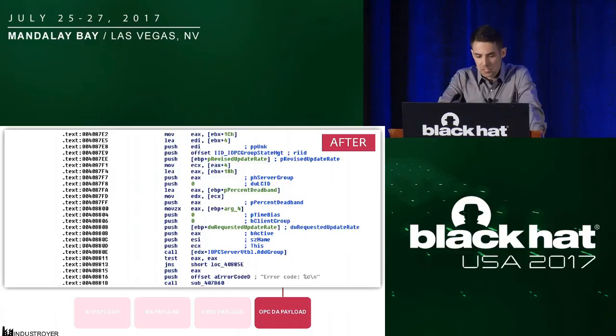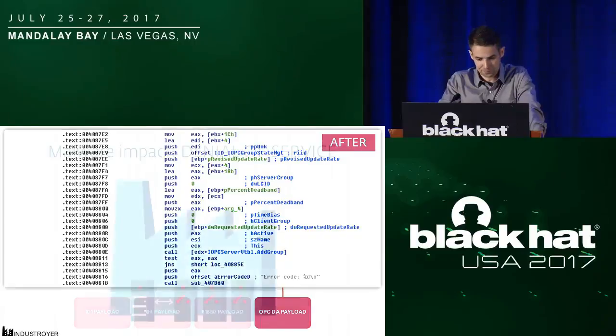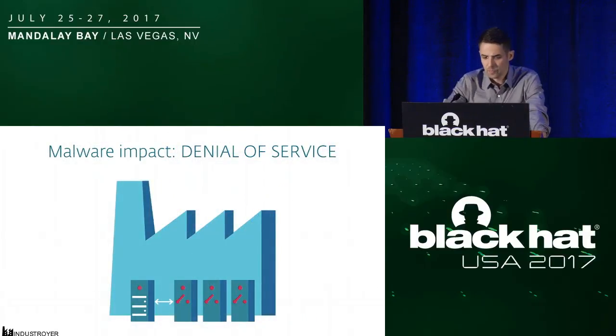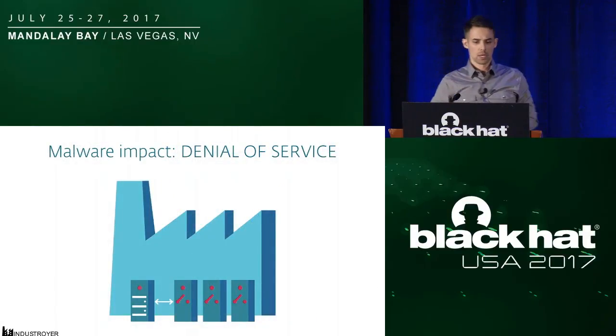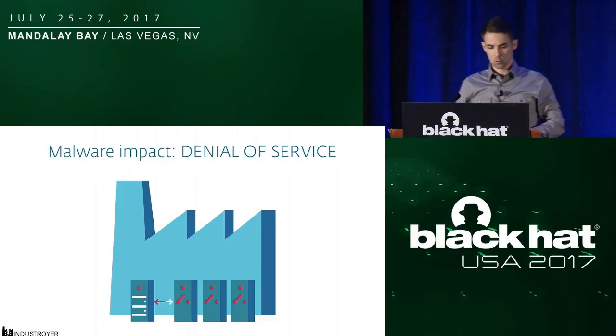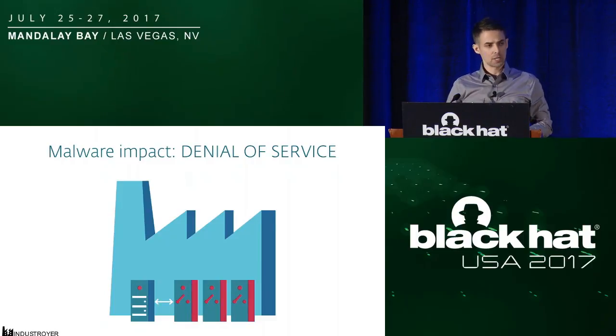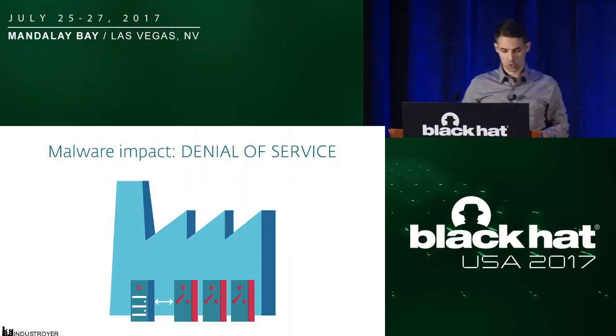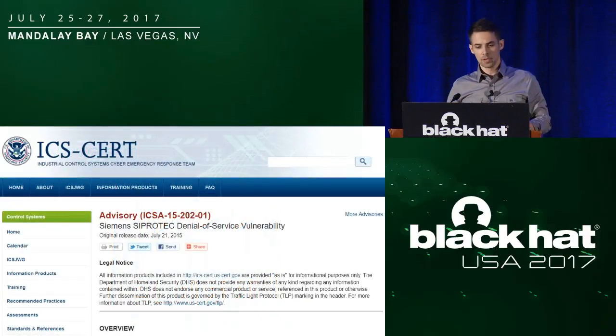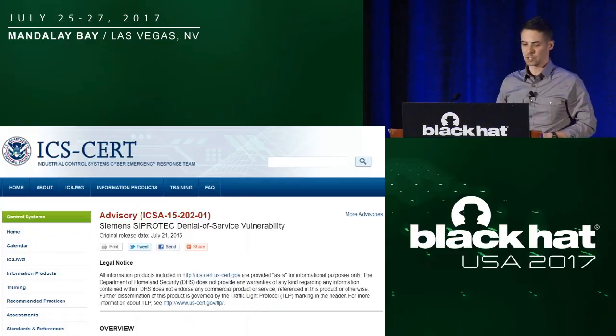De-energizing a substation is the most obvious impact scenario, and Dragos will go into more detail about that. The second type of functionality we found in Industroyer is rendering protection relays unresponsive. This is done by the denial-of-service tool I mentioned earlier, by exploiting a vulnerability in Siemens SIPROTEC devices, which is described in this ICS-CERT advisory.